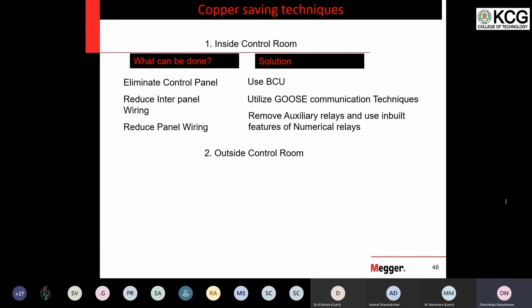Next is reduce interpanel wiring. What is interpanel wiring? There are a lot of panels which we saw in that picture. Between each panel, there will be a lot of communication, that is, a lot of information has to be transferred. That information transfer is actually through copper cables. Like, earth switch is wired in panel 1. In panel 2, I want to close the breaker. Now in panel 2, when I want to give a close command for the breaker, I have to ensure that my earth switch is open, because the breaker can be closed only when the earth switch is open.